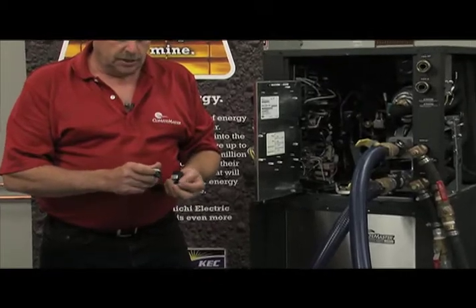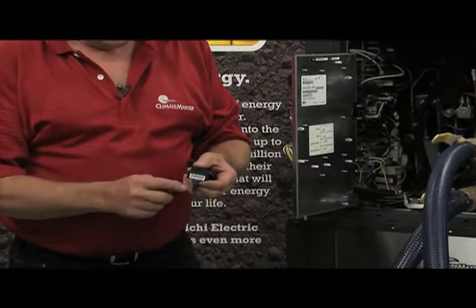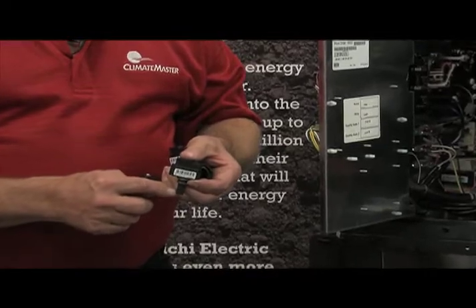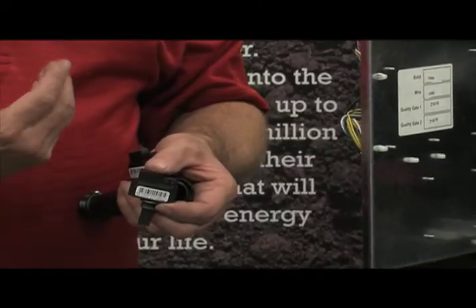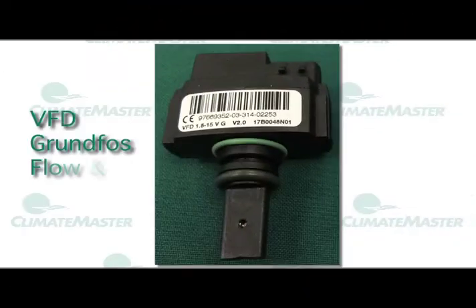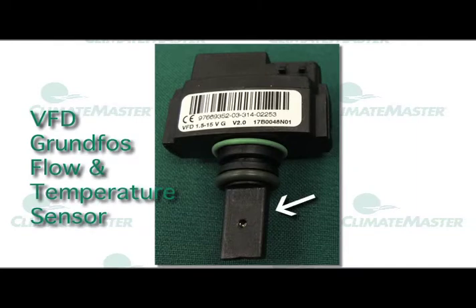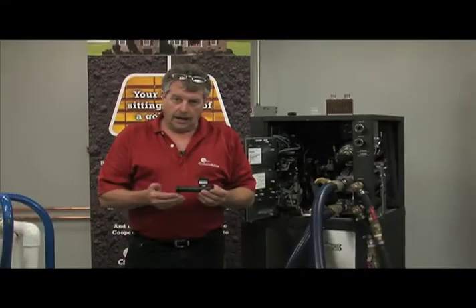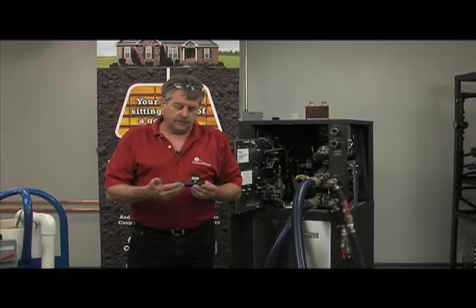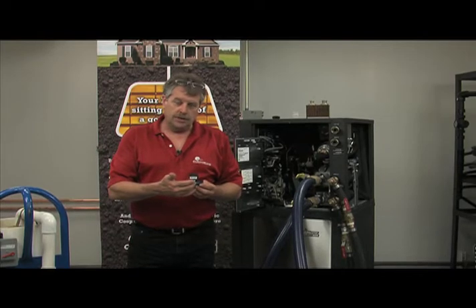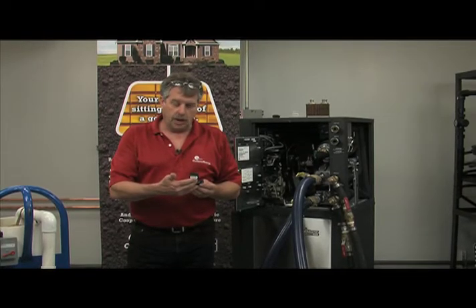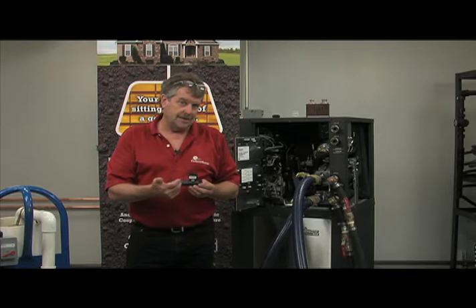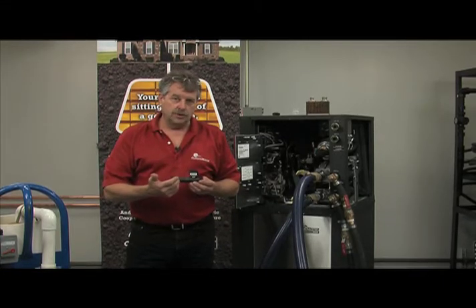Here's what the sensor looks like when it's been removed. There's a small diaphragm with a hole here, and that is essentially what is measuring that pressure difference and validating that flow. And the importance of proper flushing techniques is this: we actually have nothing but air inside this unit when you get it. There's a couple things that can compromise this. First of all, if you hit at or exceed 100 psi of pressure, you will probably compromise that sensor. The other one is if you exceed about 30 gallons a minute going through this unit.